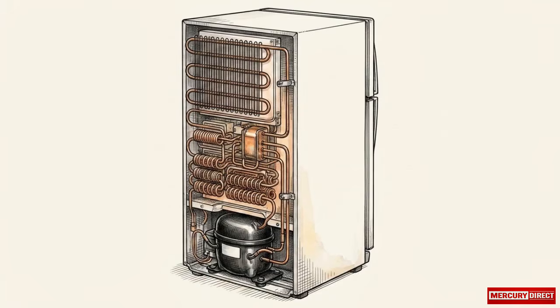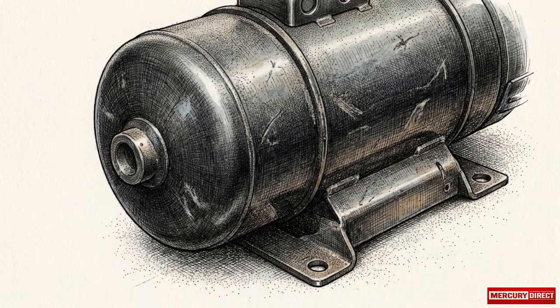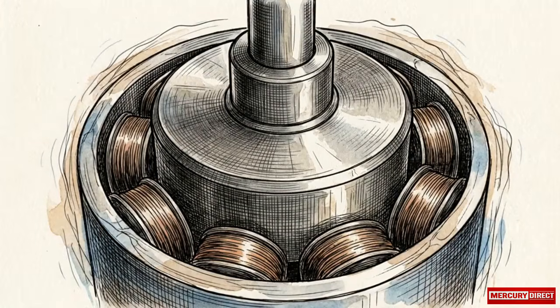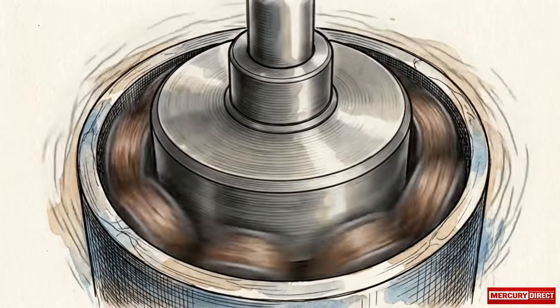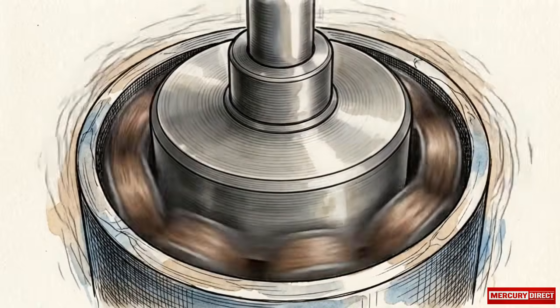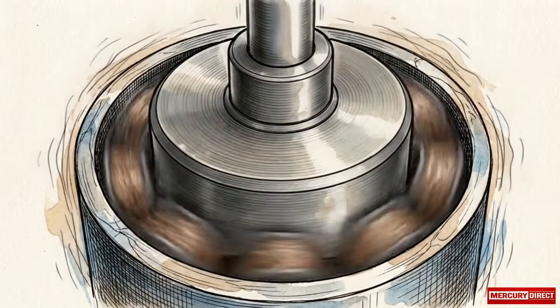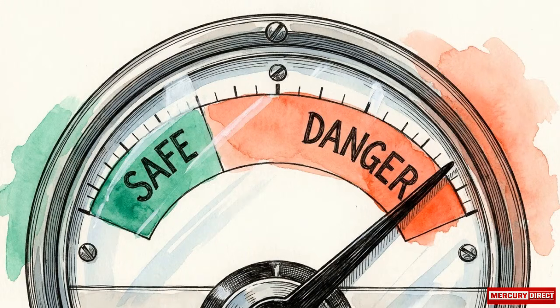To get the sizing right, you have to look at the physical mechanics of a traditional refrigerator. The real challenge has nothing to do with keeping the fridge running. It's entirely about breaking it out of a resting state. The fridge's compressor motor is heavy. Forcing that dead weight to start moving and push refrigerant demands intense energy to overcome physical inertia. To get moving, that motor pulls 3 to 5 times its normal running current.